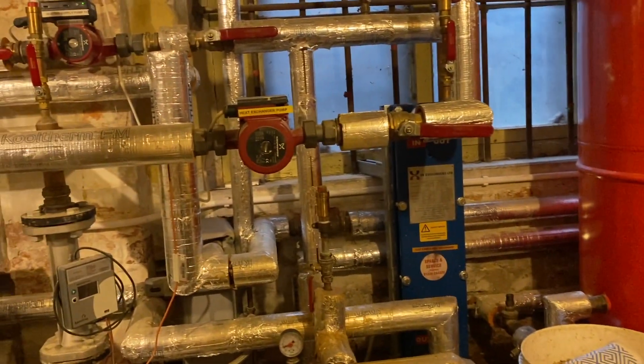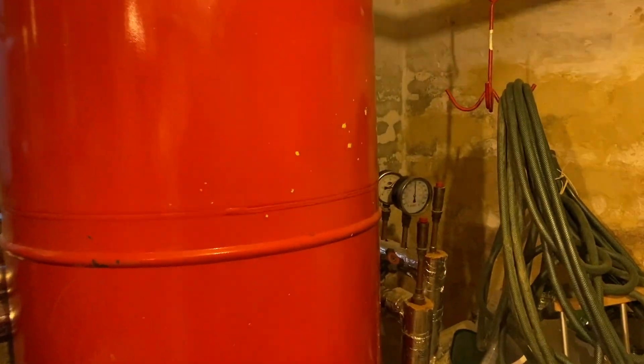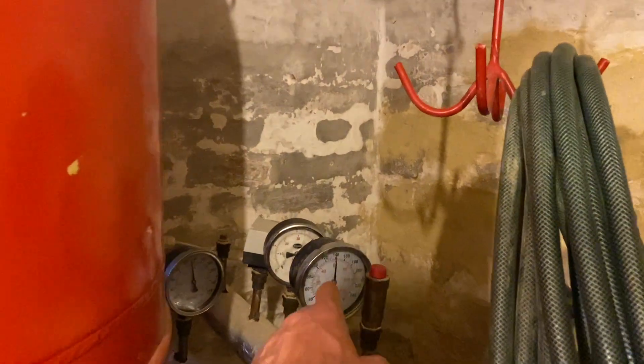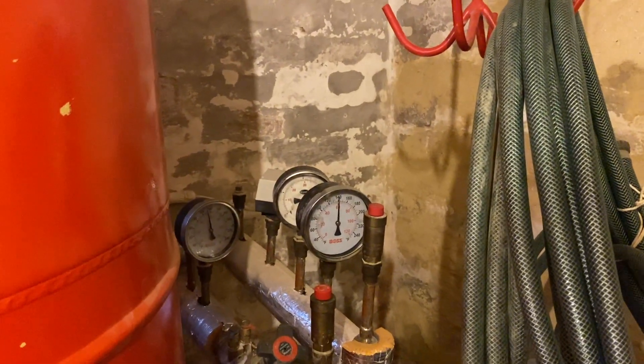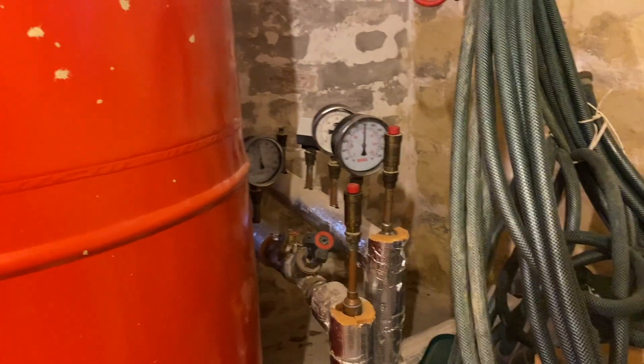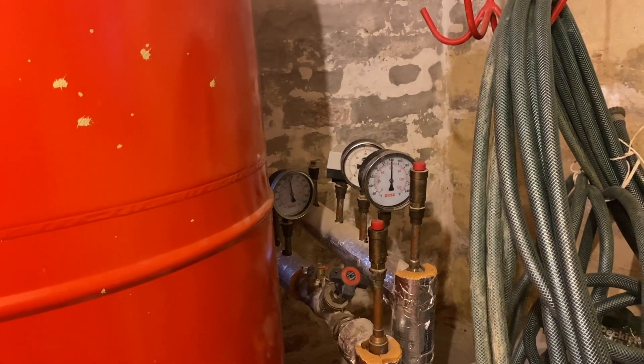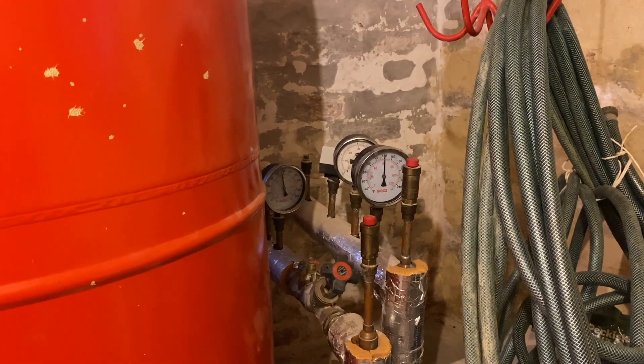The run down to the house is about 700 meters, so you'll see that it loses a fair amount of temperature coming down here on the run. I think that's probably because the pipes weren't put in correctly. And one day, if we get the energy, we'll probably dig up sections of it and try with the heat meter to see where all the heat loss is happening, because it should be a little bit warmer coming down than 60.